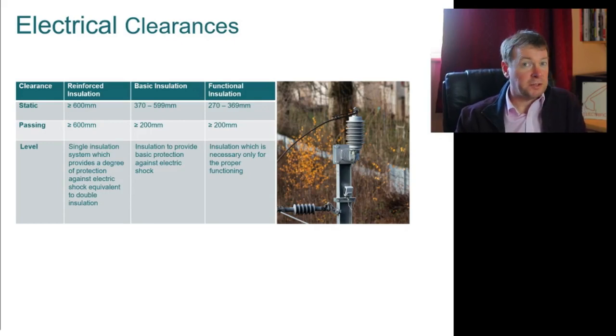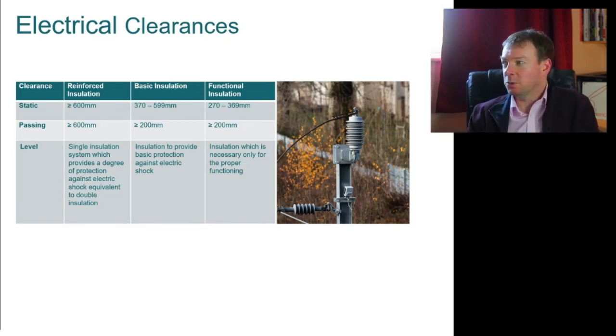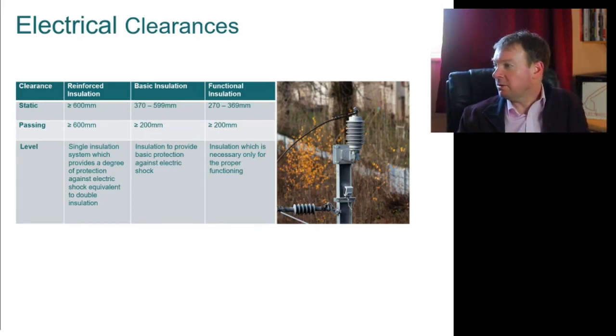The truth is, we use a lot of air gaps. We maintain air gaps between the live equipment and bridges, station canopies, signal gantries, and anything else that isn't live. So we have air gaps, and we specify the size of those air gaps, which is really important. What you're seeing on this table is the current UK standards for air gaps.